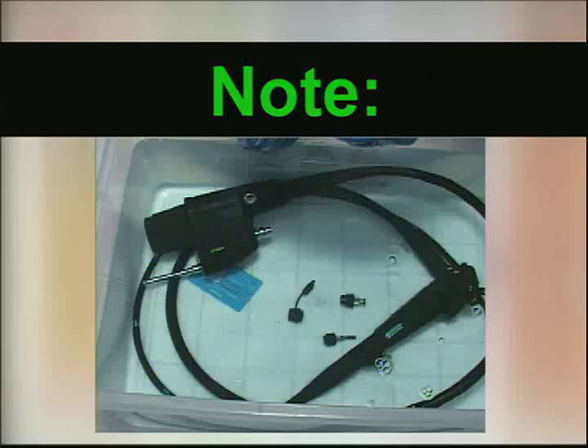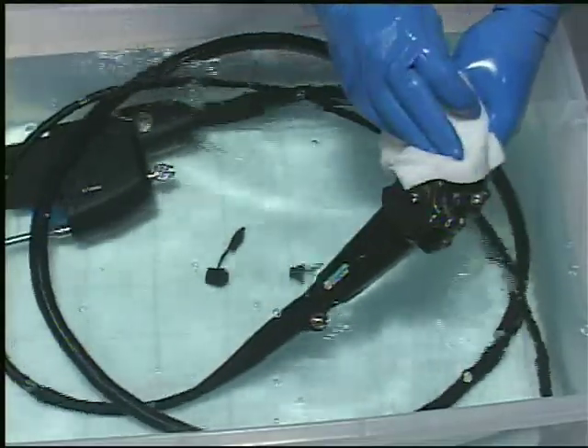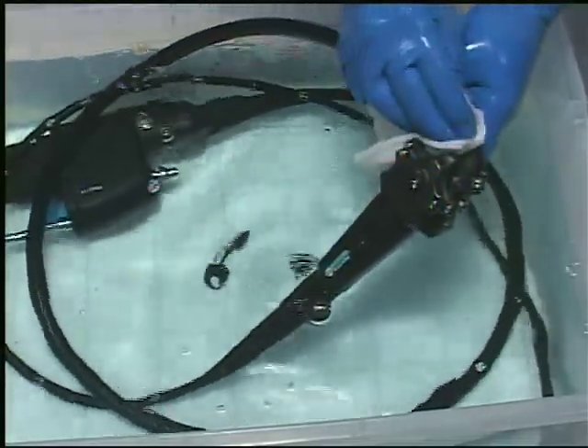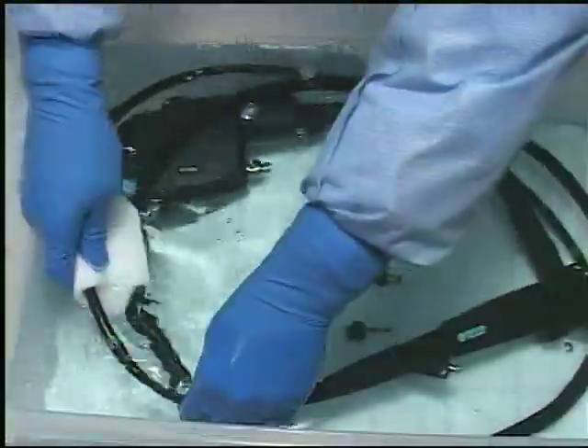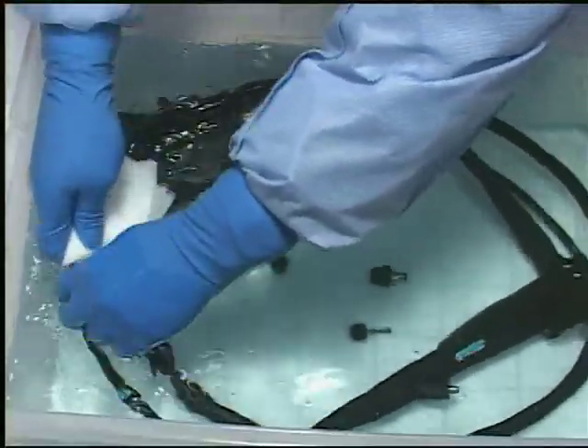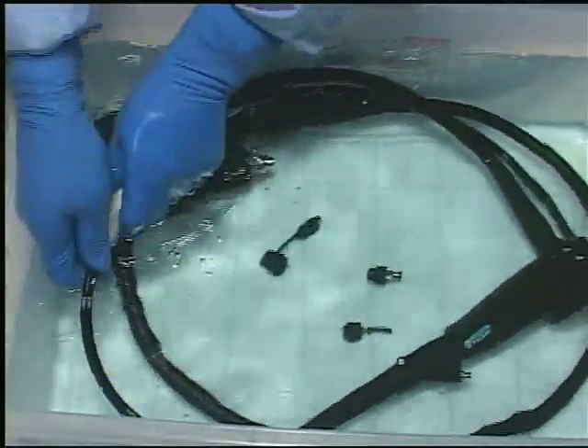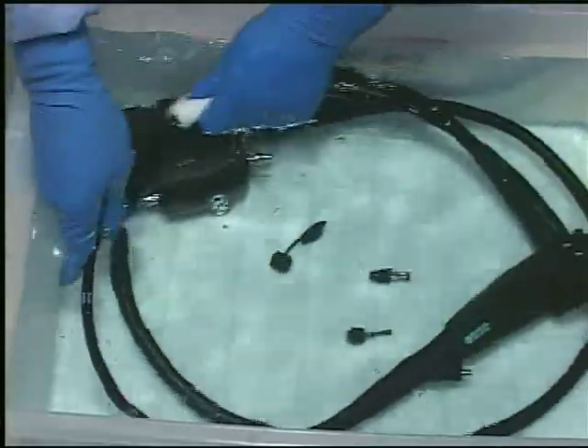Note: do not place any endoscopic accessory instruments such as biopsy forceps or other sharp-edged objects in the basin with the endoscope. Thoroughly but gently wash all external surfaces of the endoscope and scope components. Do not squeeze or severely bend the insertion tube. Do not use any abrasive materials.